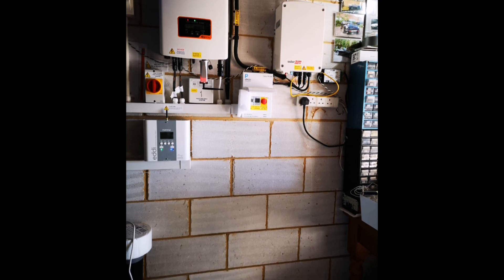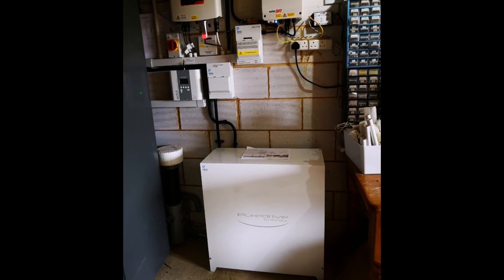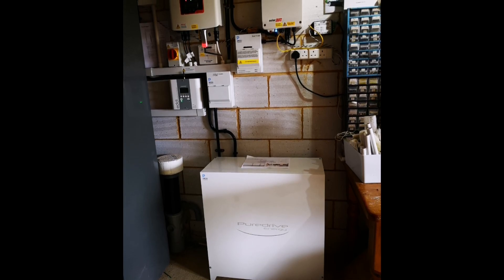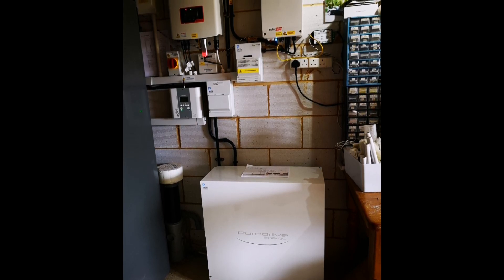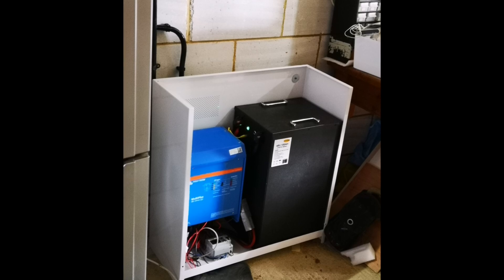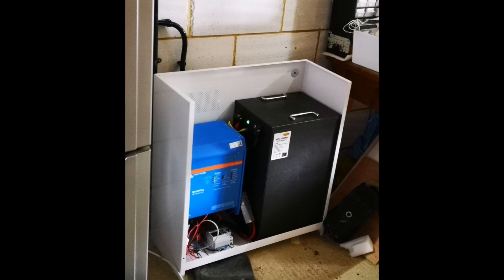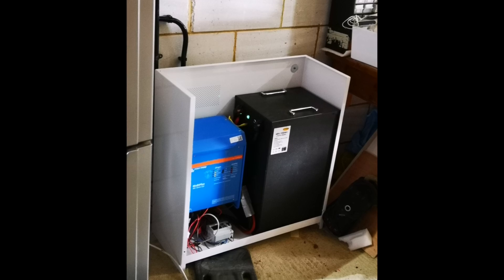This video is really about some of the teething problems installation-wise. The Power Different team — there were two of them — took about half a day to install, since this was their first time installing this unit. Probably two to three hours is what you could expect. Inside the battery case there's pretty standard stuff: the Pure Drive cabinetry, generic-looking battery cells, and a Victron inverter. Pure Drive are basically packaging some industry-standard components.